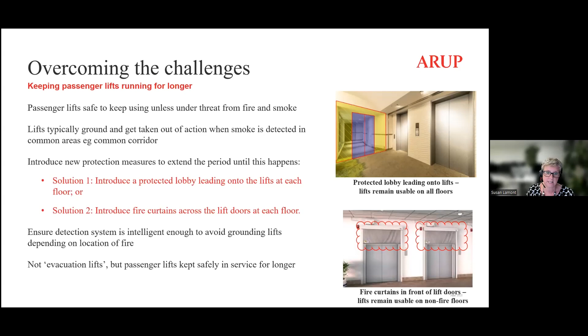To make change, retrofits and refurbishments of existing buildings will need to invest in fire safety. We've been investigating the blockers and opportunities for use of elevator evacuation in existing buildings, keeping elevators running for longer via lobby protection to allow evacuation without assistance. The feasibility of this approach is being tested as part of a desktop study across 47 properties in England, and we've found that of the 47, more than 80% can be easily retrofitted with lobby protection.